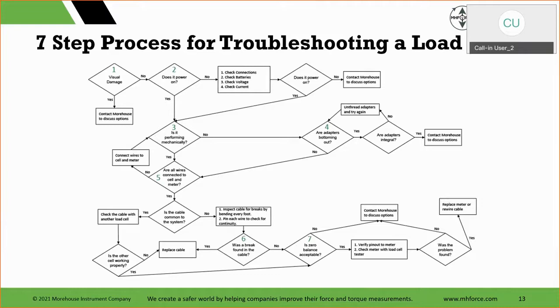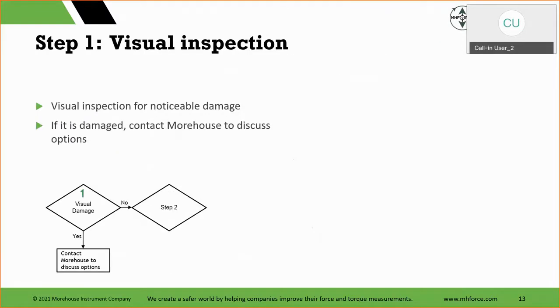discuss options. Sometimes the discussion of options is about replacement options, depending. If it's an old meter that's 20, 30 years old, or an old load cell that's 30 years old, maybe a replacement. There are some load cells that can be re-gauged, though it just depends on the size and the capacity, and that's something we can have those discussions about. But then mechanically, are our adapters bottoming out? We're going to discuss these in detail. I have pictures to go through them, but as you can see, there's the process. So visual inspection. If it is damaged, contact Morehouse to discuss options. Here, this is a great picture.